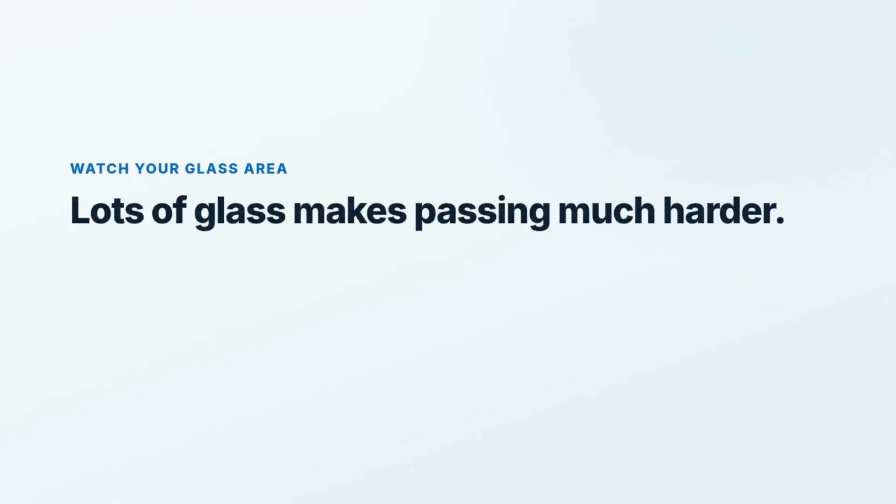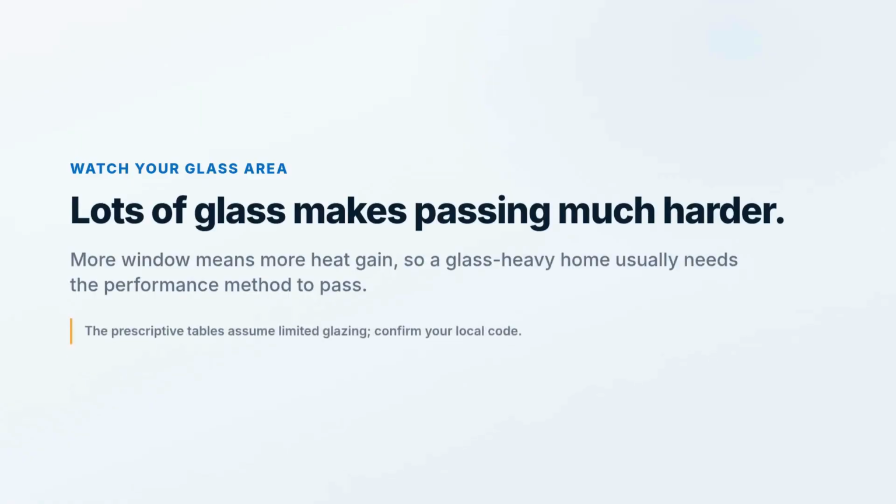Another big one in the prescriptive method that gets people, which forces us again to have to go to the performance method, is what's the percentage of window to walls. So if I take my entire surface of my walls and then I subtract out, then I take the percentage of window square footage. If the windows are greater than 20% square footage of the wall square footage under the prescriptive method, your house will fail. Now, in the performance method, if it's greater than 20%, you can still get it to pass.